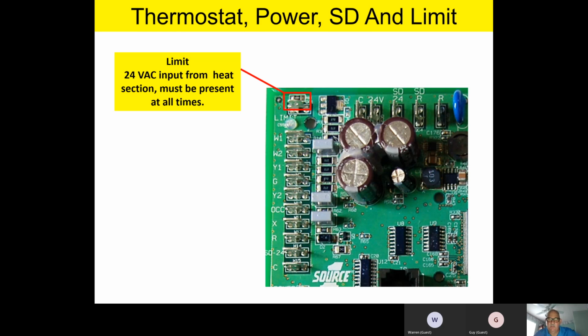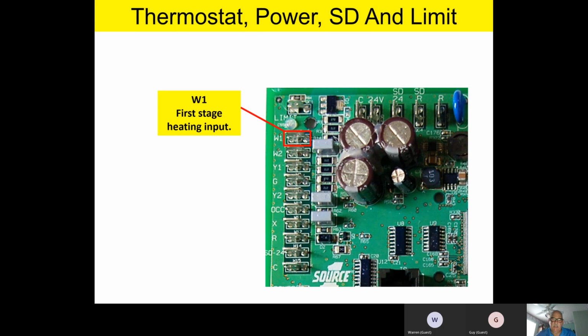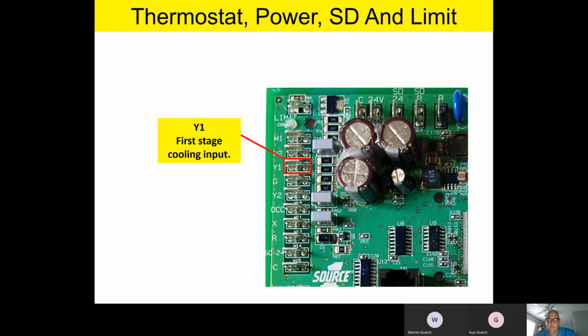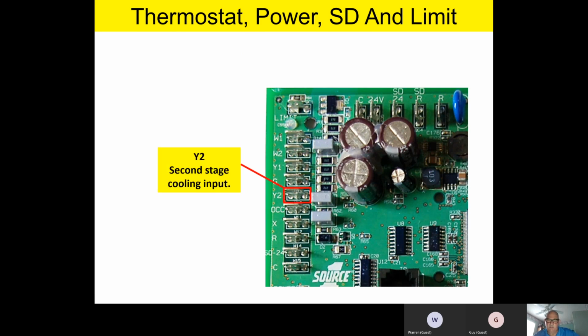As we move down the left-hand side of the board, we've removed the little screw terminals so that you can see the spade terminals a little bit better. But this is where your thermostat hooks up. And so if you have a conventional thermostat, you'll be hooking it up on these terminals right here. And so it's very, very conventional. W1 is first stage heating input. W2 is your second stage heating input. Y1 is first stage cooling on a two-stage product. G is your fan call. And again, this is very, very conventional in our industry. Nothing unusual here so far. Y2 is your second stage cooling input.